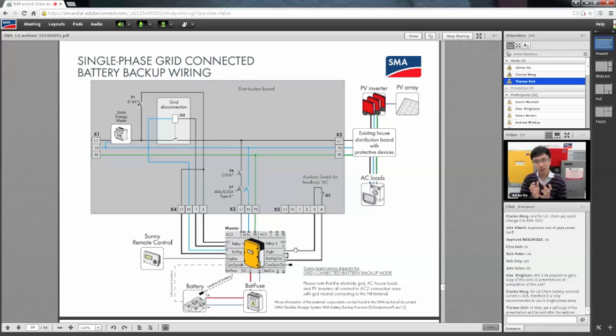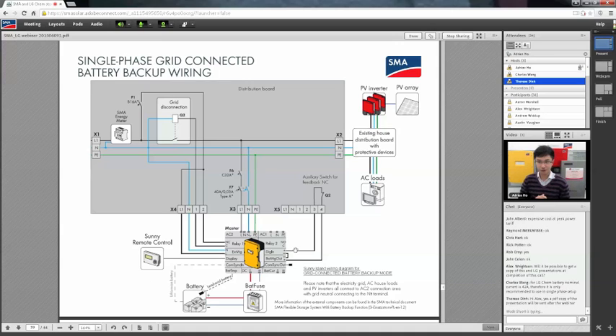Sunny Island will take around 5 seconds to boot up. Within this 5 seconds, your solar will be gone, your LG TV will be off, Foxtel will be gone. After 5 seconds, things will reboot, and Sunny Island will then provide the home with power. There's the 5 second delay because it needs to ensure it's off the grid—it can't feed power to the grid. AS4777 compliance means it can't island itself and feed power that could zap electricians out there fixing the poles and wires.